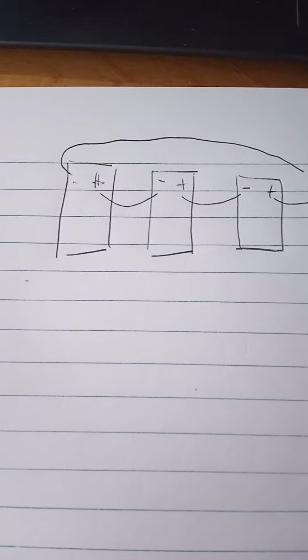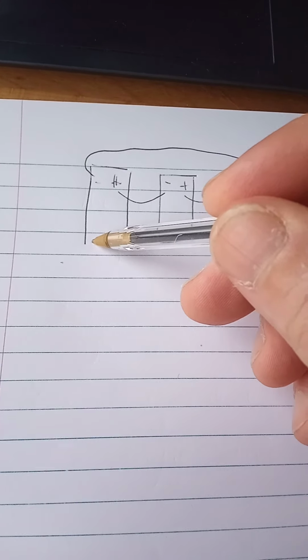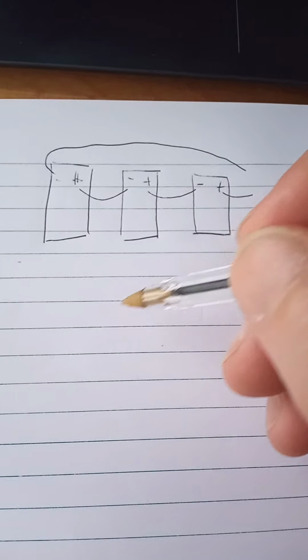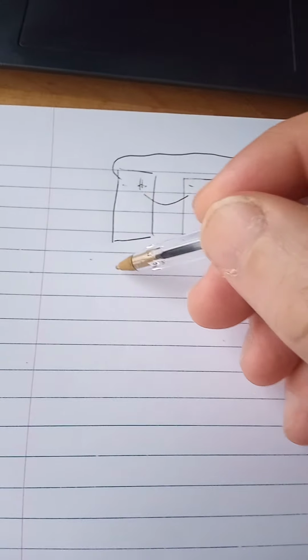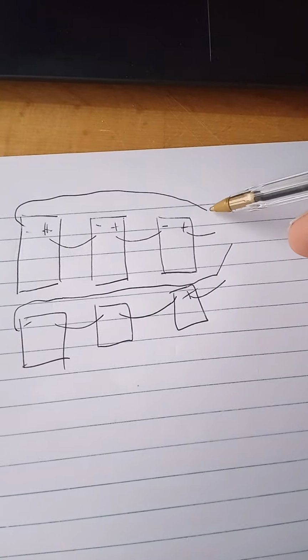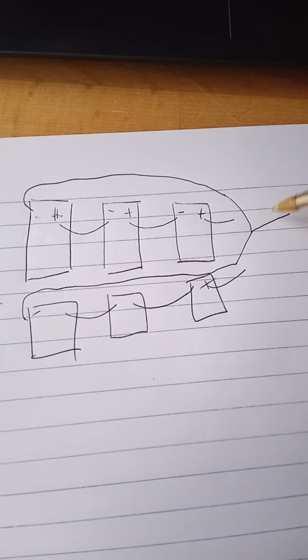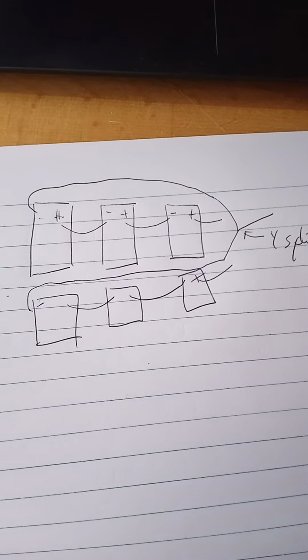What do you want to do, though, if you say you want to work at 36 volts, but you would prefer to have another line of them in parallel? Now, there's 2 things to consider here. Paralleling wires, you use splitter cables. So, for example, if I was to have another set here, and we series those together, we've got these positive here and the negative here coming round. Now I've got 2 negatives and 2 positives to bring together, and your Y splitter is what does that. So that's a Y splitter point there. Okay, and that's using an MC4 connection.